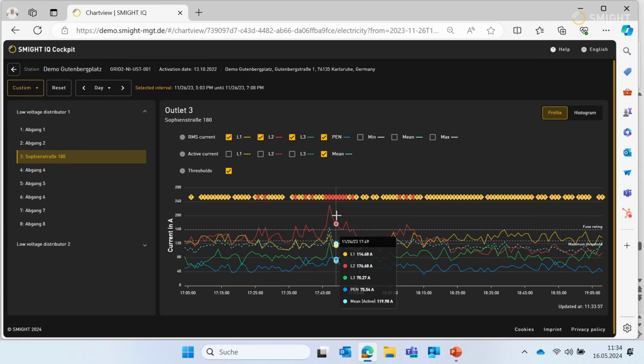But what this particular customer did is go out and perform a switching action to move the load onto another feeder. So this was an overloaded feeder, and they switched the load to another feeder, reducing the load on this specific problem feeder.